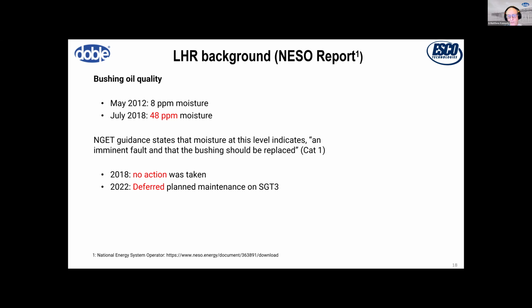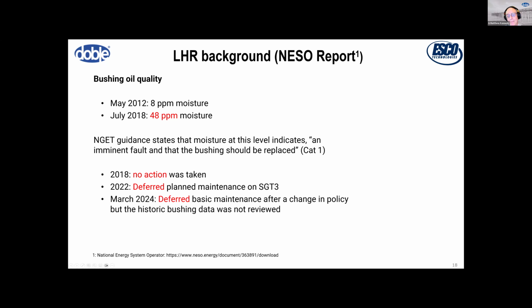Well, in 2022, they deferred the planned maintenance again. Things were busy. They planned the maintenance on SGT3, and unfortunately again in March 2024, they deferred the basic maintenance after a change in policy, but the historic bushing data was not reviewed. In other words, they were reviewing the transformer, but not the bushing. Remember, we talk about how models are sometimes compounded on top of each other, and that was just not considered in this case.